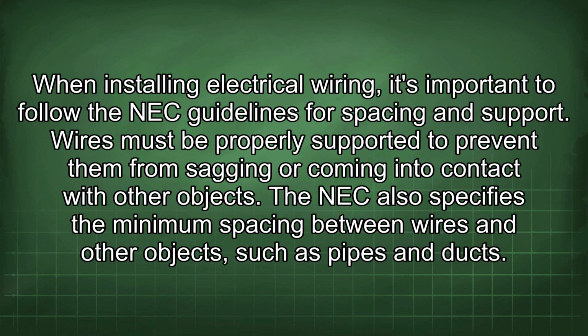When installing electrical wiring, it's important to follow the NEC guidelines for spacing and support. Wires must be properly supported to prevent them from sagging or coming into contact with other objects. The NEC also specifies the minimum spacing between wires and other objects, such as pipes and ducts.